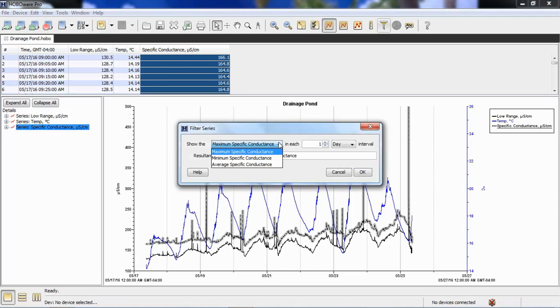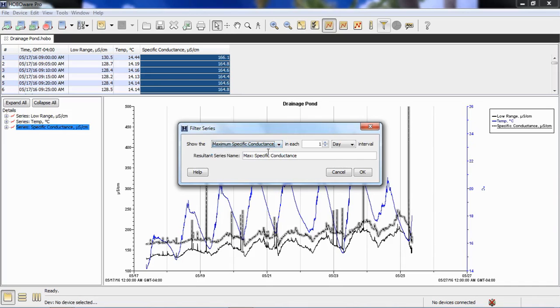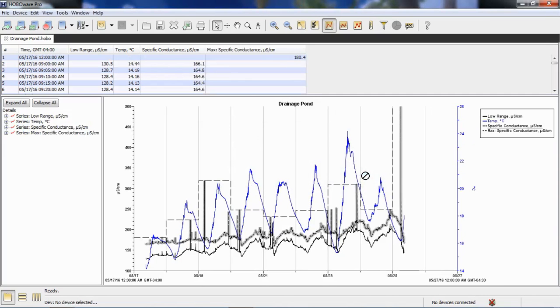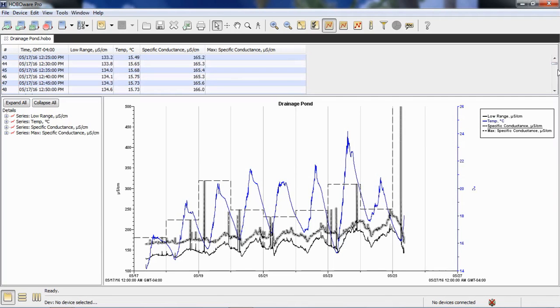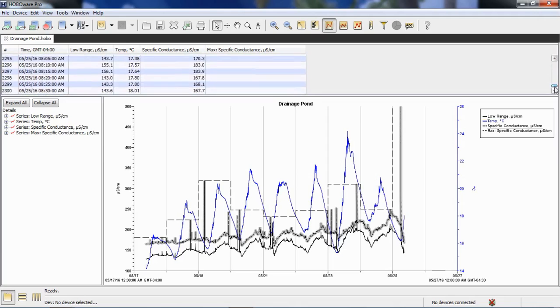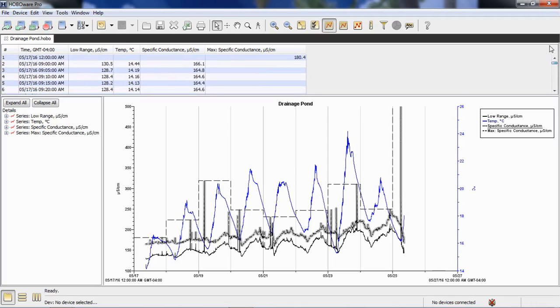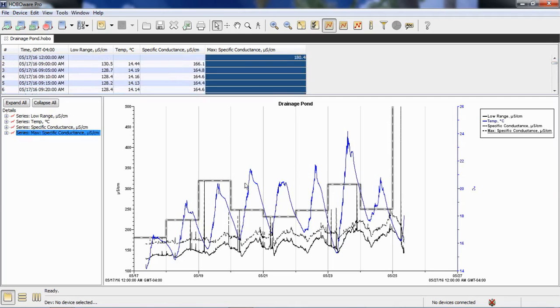And we have three filter criteria available, max, min, or average within a specific time period based on those five minute intervals of data. So, I want to see what my maximum specific conductance was in each 24-hour period. Click on OK. And now I have a column that includes one reading for each day that corresponds to the maximum value that it saw each day. So, you can see it's kind of a stair-step effect, and it is reported from midnight to midnight, but it's based on that 24-hour period.